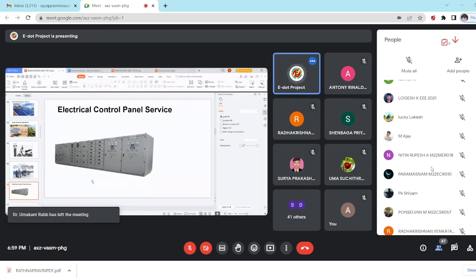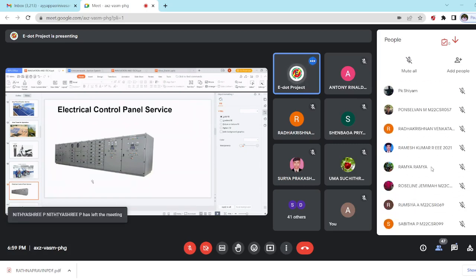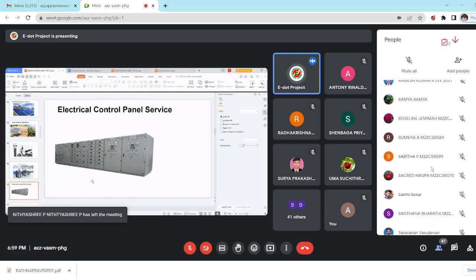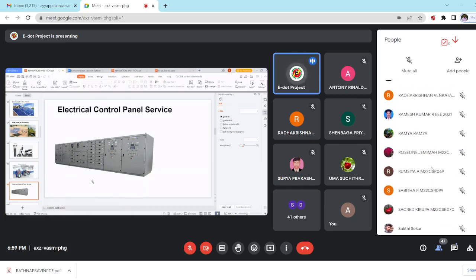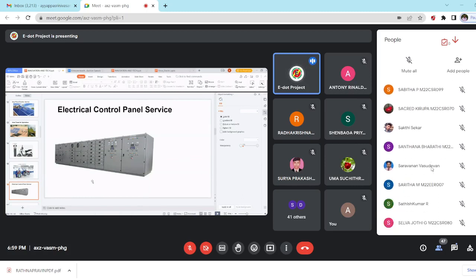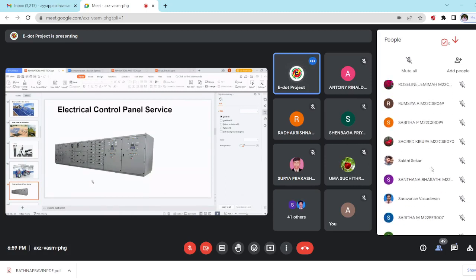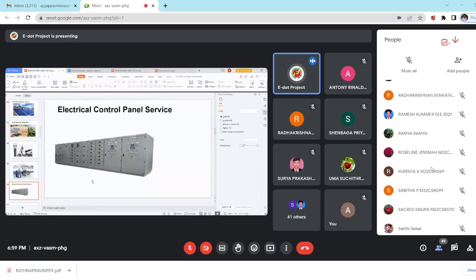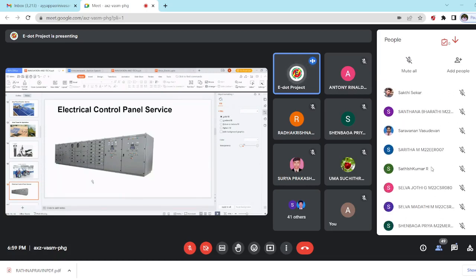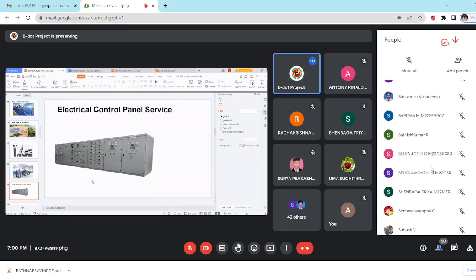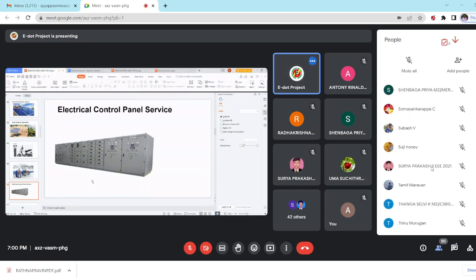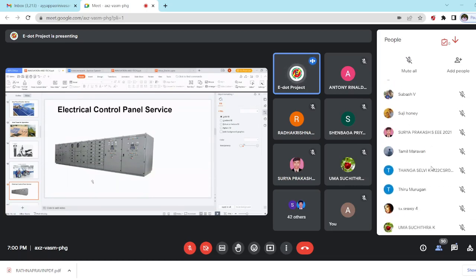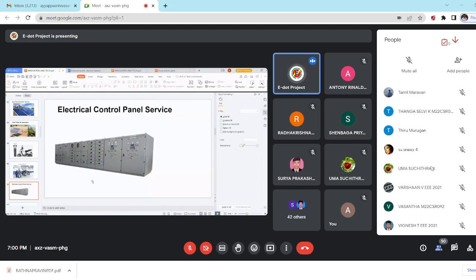Then the fourth one is logging, monitoring and recording panels, meaning SCADA, DCS, like this. So the fourth control panel system is the SCADA system, logging system, monitoring system. Input power, output power, input power factor, output power factor, so many data are continuously monitored: the voltage level, whether the generator is on or off, how much power the solar panel is producing. So many things are monitored in the control panel, so we need a monitoring, data logging and reporting system.